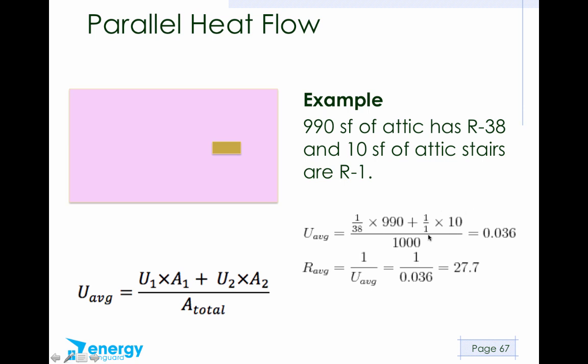So 990 divided by 38 gives us the first part. Then we do this part. 1 over 1 is 1. 1 times 10 is 10. So we've got 10 here. When we do 990 divided by 38, we get 26, and 26 plus 10 is 36. 36 divided by 1,000 is 0.036. So that is our average U value. But if we want to know what the average R value is, we just do 1 over U average. So 1 divided by 0.036, you get 27.7. The takeaway here is that 1% uninsulated area can have a huge effect on your heat flow, because that knocks your R value of that R38 attic down from R38 to R28.